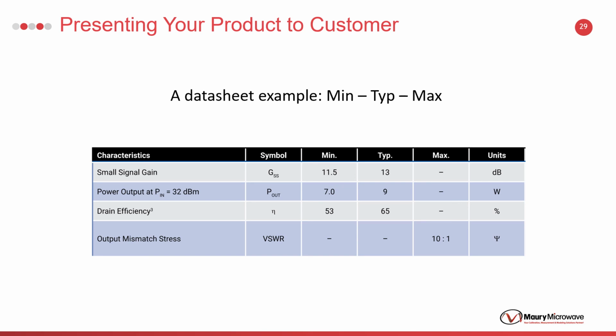How do you present your measurement data to your customer? If we look at data sheets, we see three values for each parameter: minimum, typical, and maximum values. The presented data do not show the weights of the contributions causing the variation. Presenting additional information with uncertainty will provide more confidence on data sheets. Uncertainty information can be included with statistical analysis to verify if devices produced in mass quantities meet the acceptance criteria.